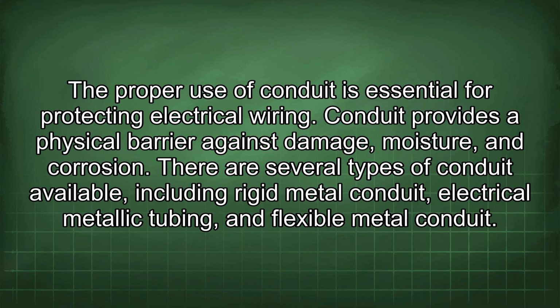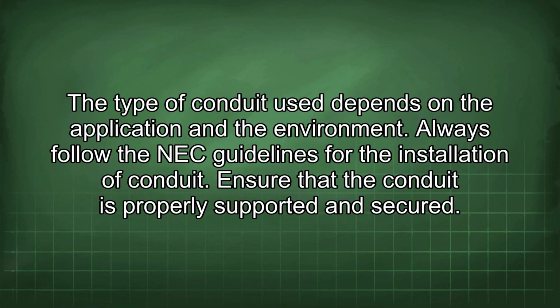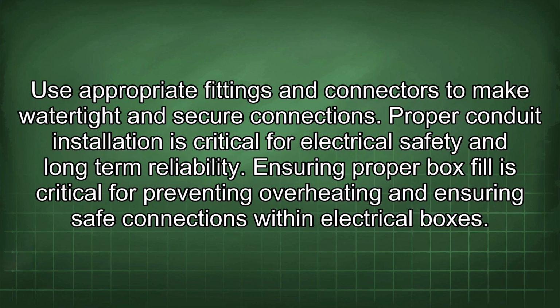The proper use of conduit is essential for protecting electrical wiring. Conduit provides a physical barrier against damage, moisture, and corrosion. There are several types of conduit available, including rigid metal conduit, electrical metallic tubing, and flexible metal conduit. The type of conduit used depends on the application and the environment. Always follow the NEC guidelines for the installation of conduit. Ensure that the conduit is properly supported and secured. Use appropriate fittings and connectors to make watertight and secure connections. Proper conduit installation is critical for electrical safety and long-term reliability.